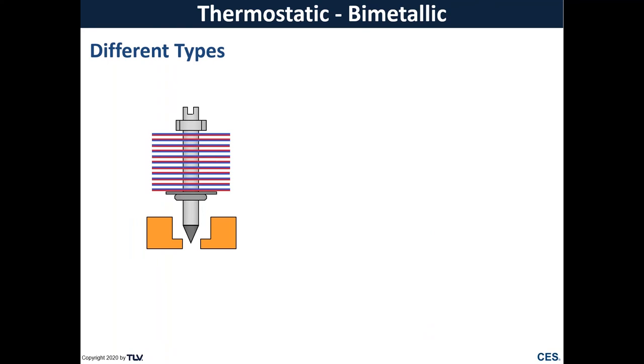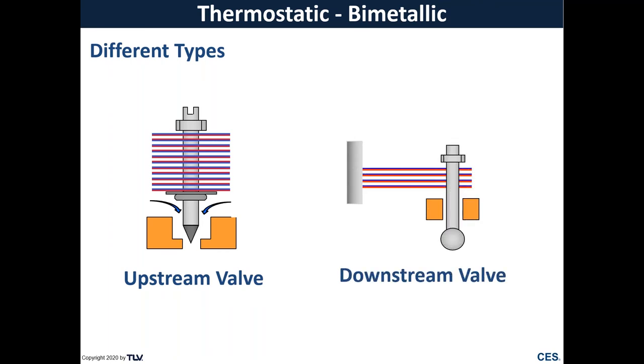There are a few different valve types that I'd like to cover, one being an upstream valve head. The valve head is going to seat on the upstream side of the seating surface. And on the other side, you have your downstream valve head. This valve head is going to seat on the downstream seating surface of the seat.